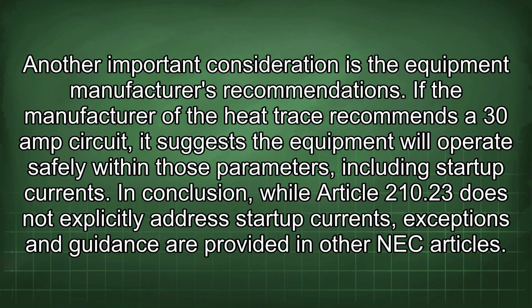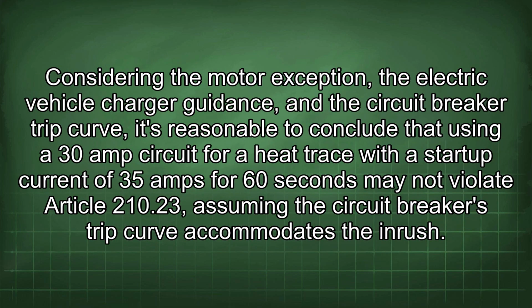Another important consideration is the equipment manufacturer's recommendations. If the manufacturer of the heat trace recommends a 30 amp circuit, it suggests the equipment will operate safely within those parameters, including startup currents. In conclusion, while Article 210.23 does not explicitly address startup currents, exceptions and guidance are provided in other NEC articles. Considering the motor exception, the electric vehicle charger guidance, and the circuit breaker trip curve, it's reasonable to conclude that using a 30 amp circuit for a heat trace with a startup current of 35 amps for 60 seconds may not violate Article 210.23, assuming the circuit breaker's trip curve accommodates the inrush.